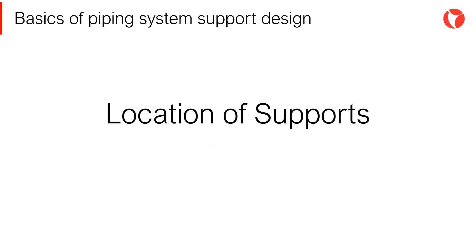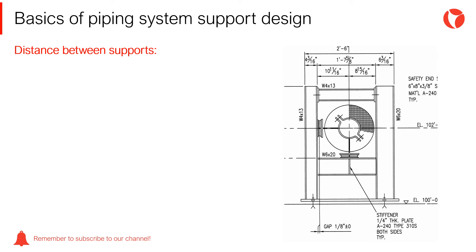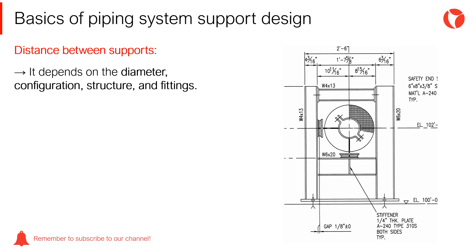The allowable spans between supports of horizontal lines are mainly limited by the longitudinal forces that must be kept within limits, or in some cases by the maximum deflection. In other special cases, the span can be limited to control the natural frequency of the pipe so as to avoid undesirable vibrations. Basically, the distance between supports depends on the diameter, configuration, structure, and fittings.